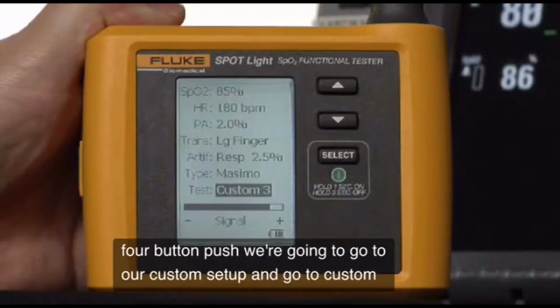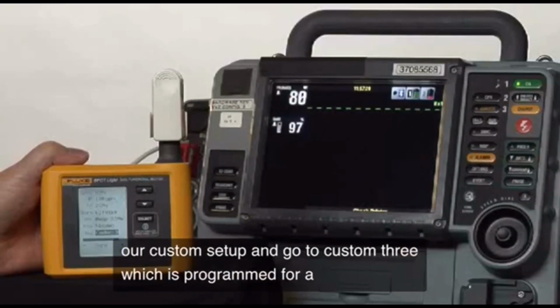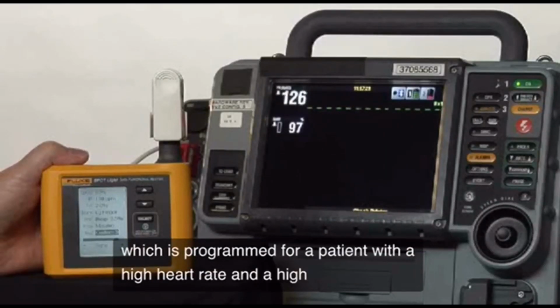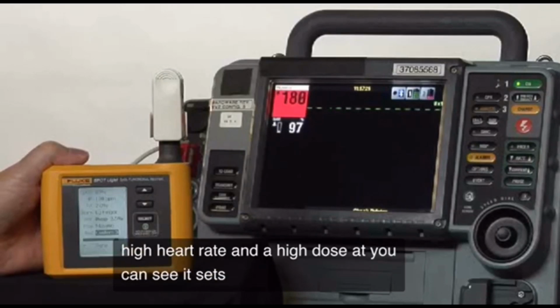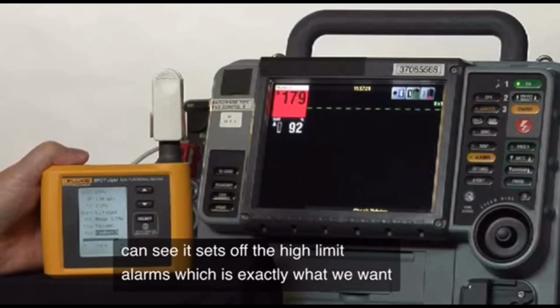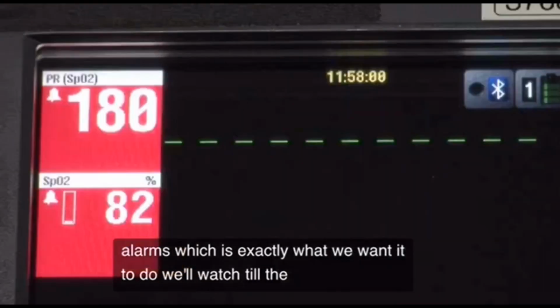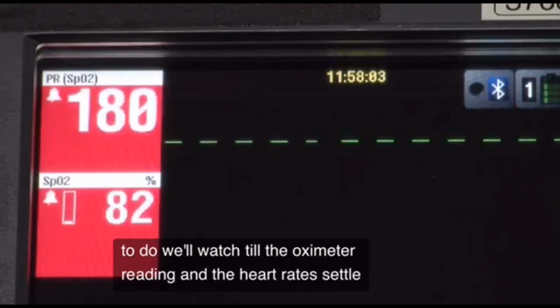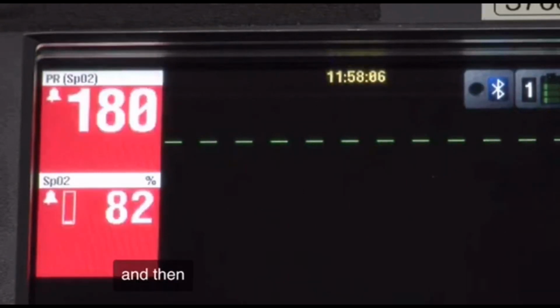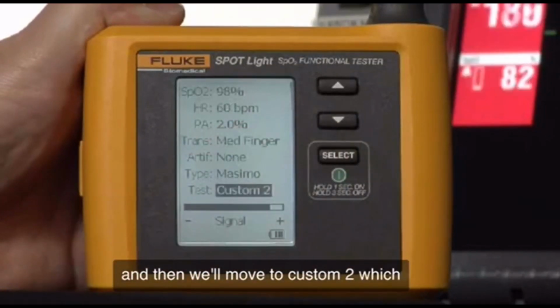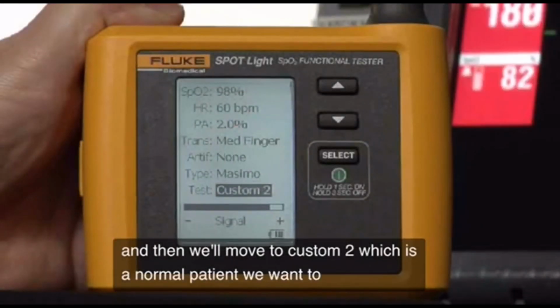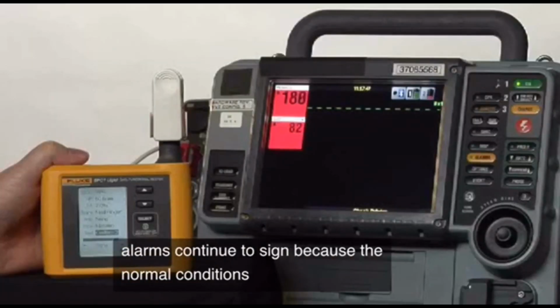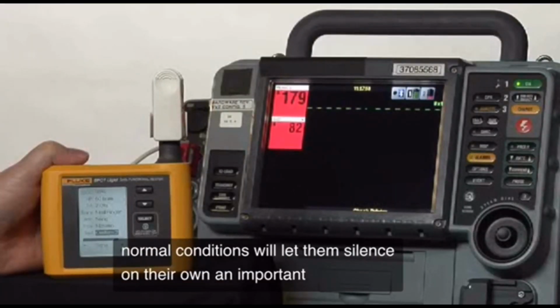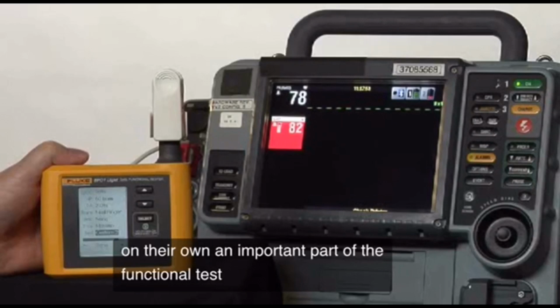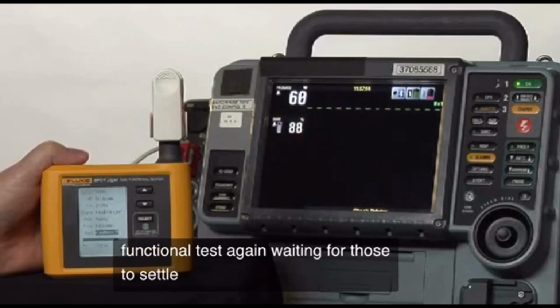We're going to go to our custom setup and go to Custom 3, which is programmed for a patient with a high heart rate and a high O2 sat. You can see it sets off the high limit alarms, which is exactly what we want it to do. We'll watch till the oximeter reading and the heart rate settle. And then we'll move to Custom 2, which is a normal patient. We want to let the alarms continue to sound because the normal conditions will let them silence on their own, an important part of the functional test. Again, waiting for those to settle.